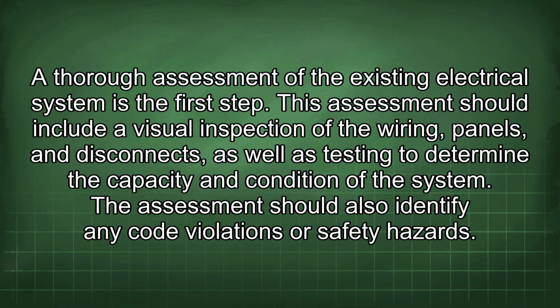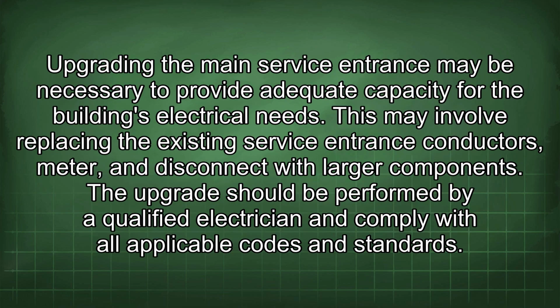A thorough assessment of the existing electrical system is the first step. This assessment should include a visual inspection of the wiring, panels, and disconnects, as well as testing to determine the capacity and condition of the system. The assessment should also identify any code violations or safety hazards. Upgrading the main service entrance may be necessary to provide adequate capacity for the building's electrical needs. This may involve replacing the existing service entrance conductors, meter, and disconnect with larger components. The upgrade should be performed by a qualified electrician and comply with all applicable codes and standards.